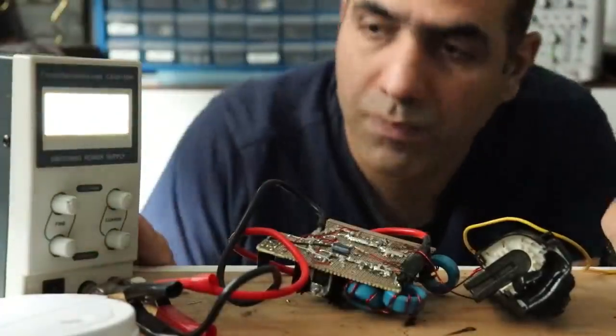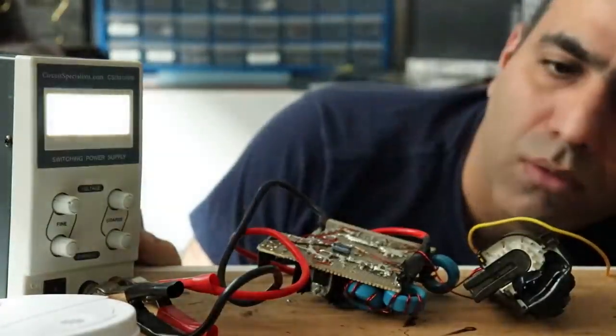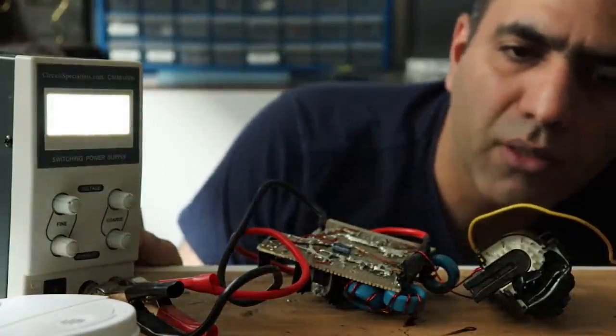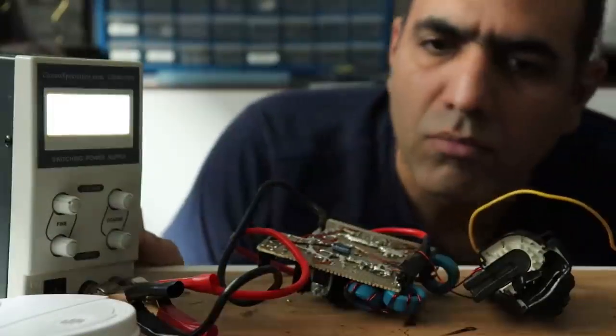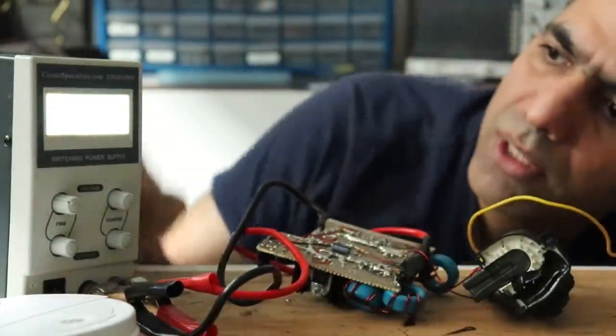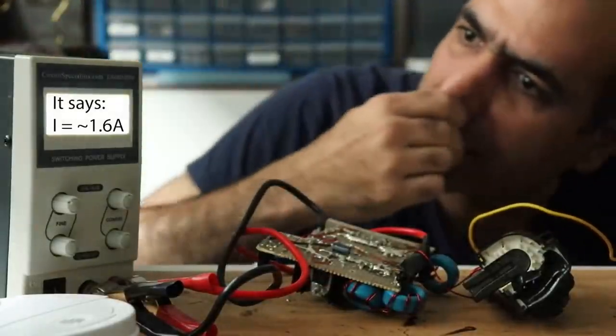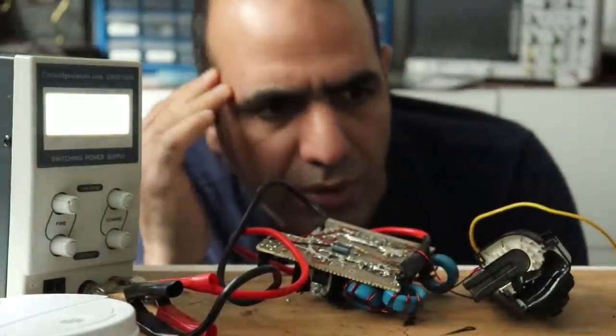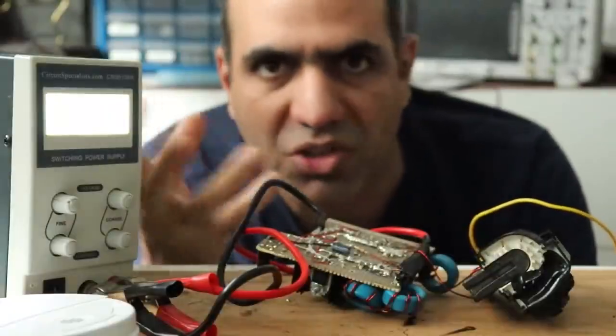Okay, here we are. Ooh, it's making some noises and it smells like ozone. But it's only drawing 1.6 amps. So the other transformer was broken and probably arcing internally—that's why it burned.